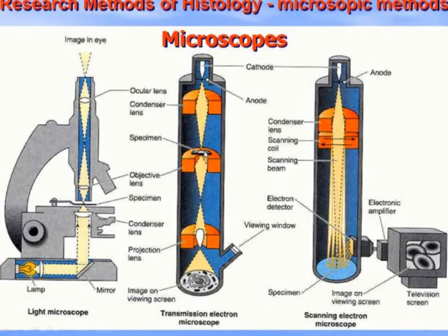We concentrate the beam of electrons onto the specimen, then it is increased by a magnetic field, the objective, like an objective lens, and the magnification is increased by another magnetic field as a projection lens, and the increased image of the specimen appears at the fluorescence viewing screen, and you can see it through the viewing window.